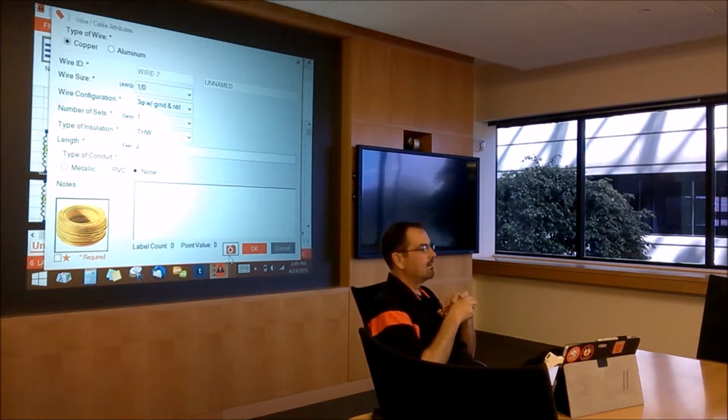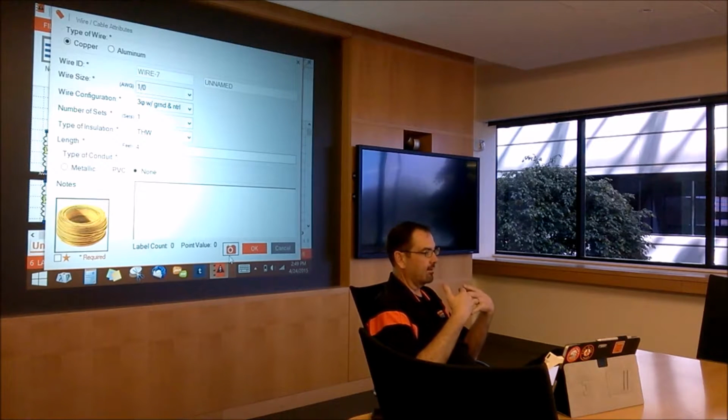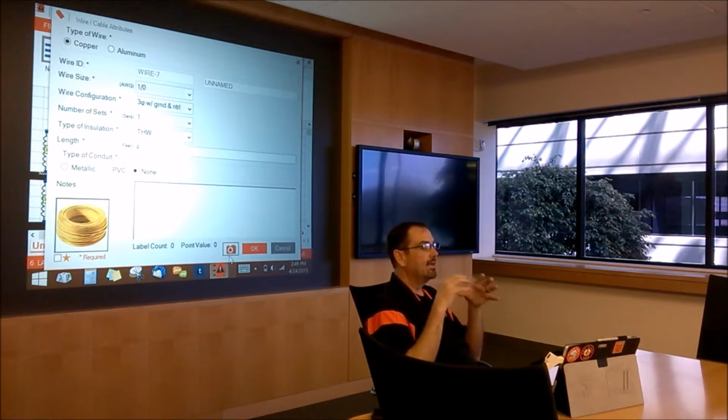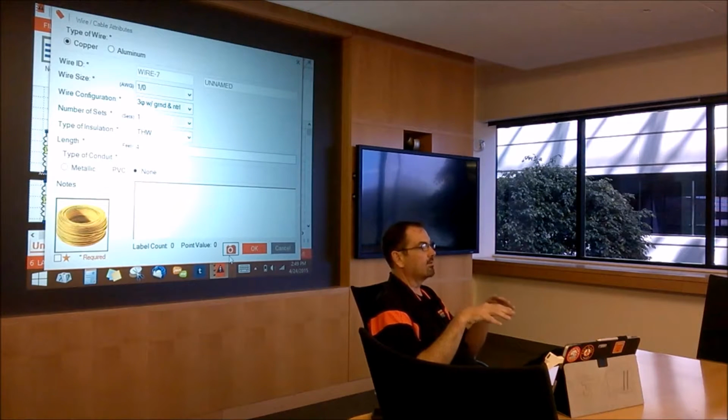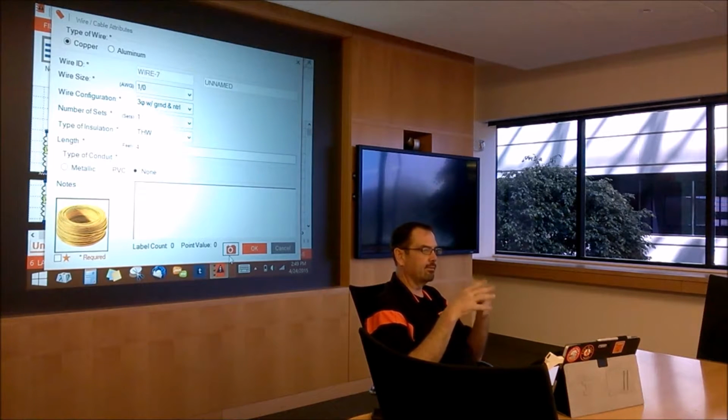Exactly, yeah. So in working with different contractors over the years, sometimes they're organized, sometimes you get 32 different emails with piecemeal information, and it's tough to make heads or tails. All right. The better thing is that in our process with doing our flash, once we receive the information back up to FlashTrack, we take that, interpret it, and get it back down to the contractor that did the data collection for further review. There's always, I'd say almost 100% of the time, a question on there. There's something that just isn't right. It's usually a code violation, and that code violation is usually a wire issue with the protective device.